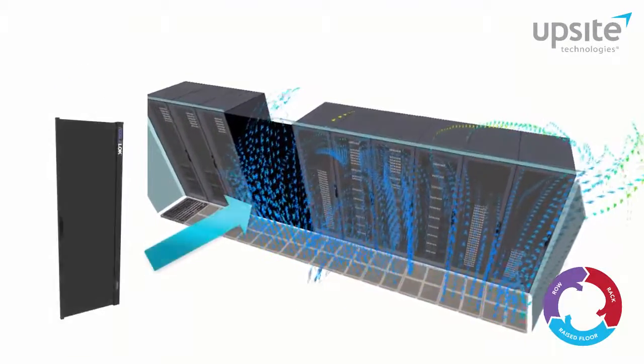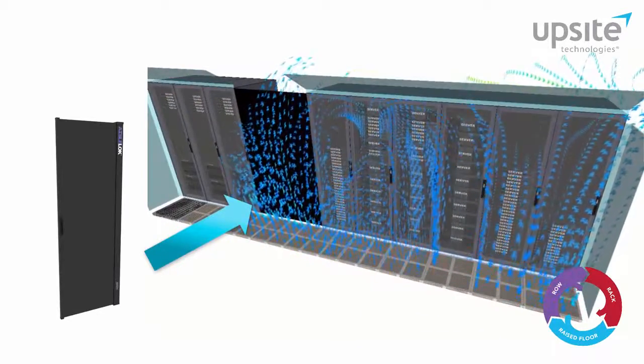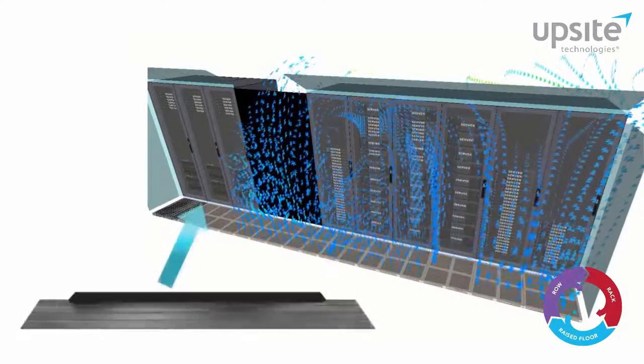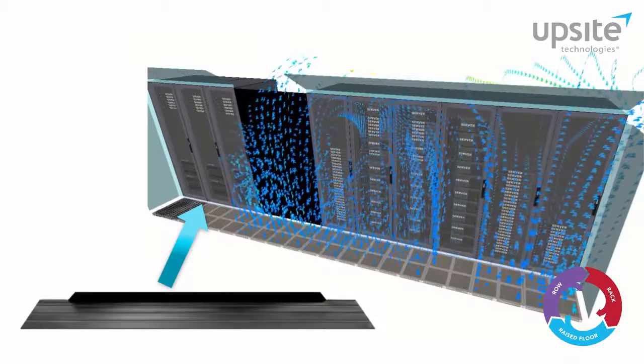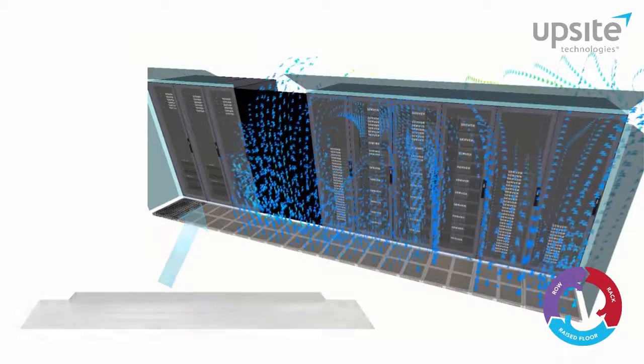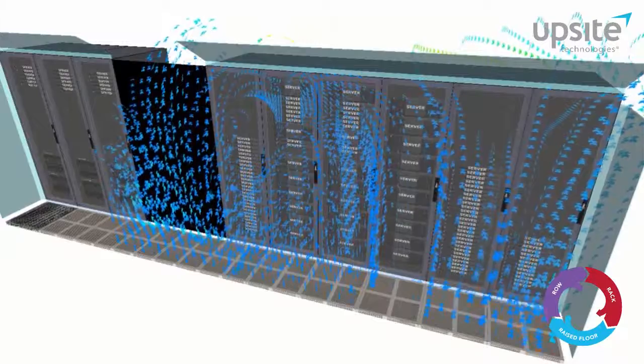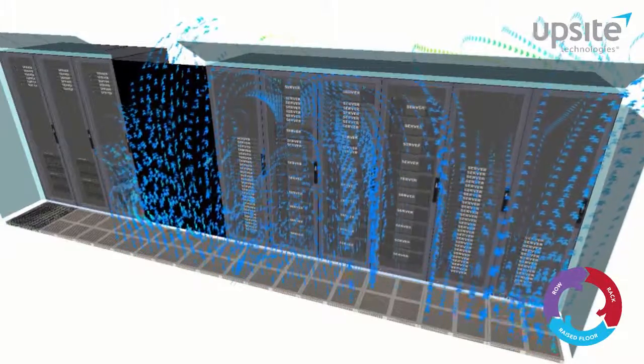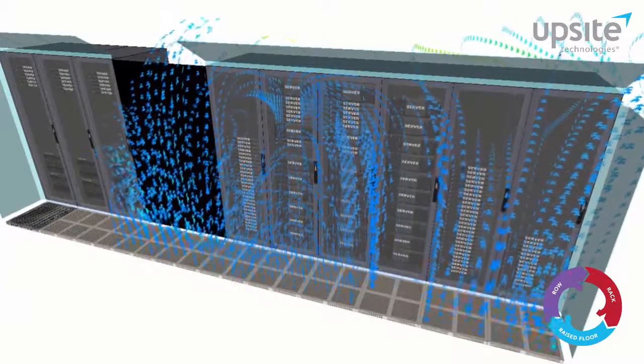Additionally, AisleLock adjustable rack gap panels are attached where racks are missing, and AisleLock under-rack panels seal the open space between the floor and the bottom of the rack. Once the AisleLock products are installed, CFD analysis reveals that the cold aisle is free of hot exhaust air.